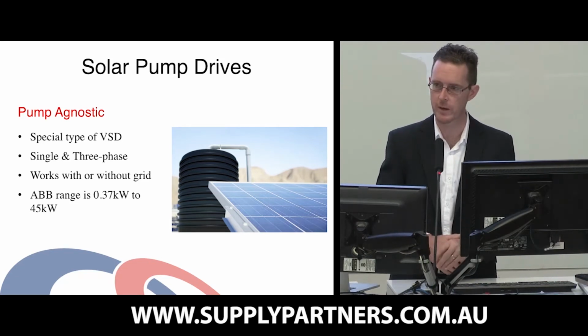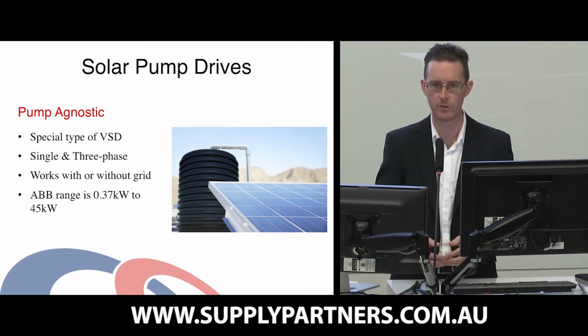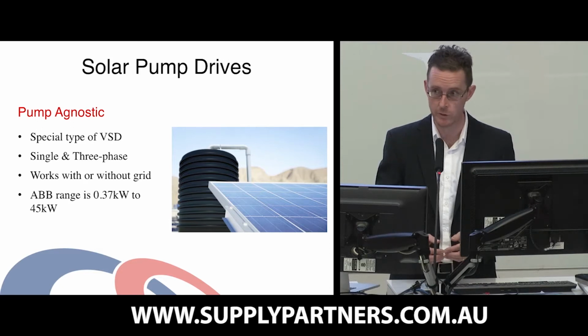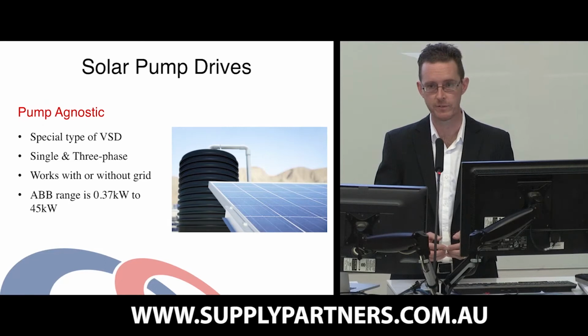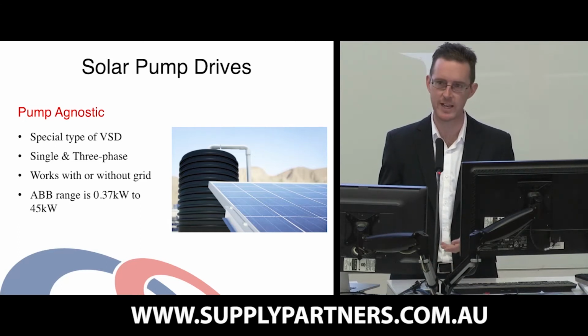ABB's range of pump drives extends up to 45 kilowatt three-phase. We've had a customer recently of ours install a 30 kilowatt drive running a 22 kilowatt pump outside of Bowen in northern Queensland. And one of the pieces of feedback we received from that project is that the customer was really impressed that the pump drive, because it understands pumps and motors, was able to identify if the pump got clogged, it would automatically run the pump backwards and forwards 3 times to flush it out.